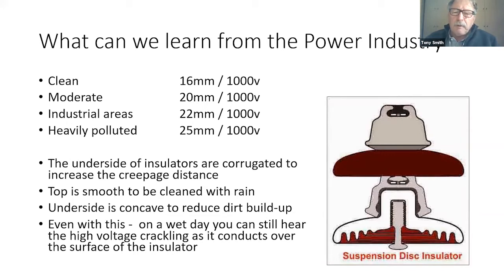Being outdoors, it gets dirt on it and wet in the rain, so it starts to conduct. So they've made the top self-cleaning, and the bottom has a long tortuous corrugated path. The actual creepage distance is quite a lot longer than the shortest air path, the clearance distance.